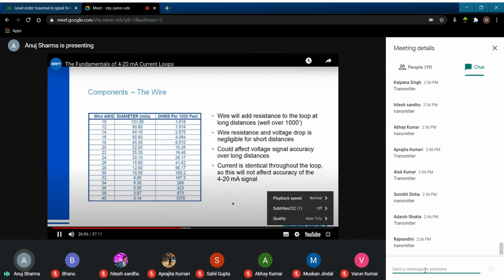If you're using standard 12 gauge wire and run 1,000 feet of it, you only get 1.6 ohms. Even at 20 milliamps, if you walk through the voltage drop equals current times resistance equation, you'll see you drop around 30 millivolts over that 1,000 feet of wire. If you're using a 24 volt supply, 30 millivolts won't cause a problem. And unlike a voltage signal in control systems, because current is the same everywhere in the loop, you don't get any added inaccuracy from that voltage drop either.